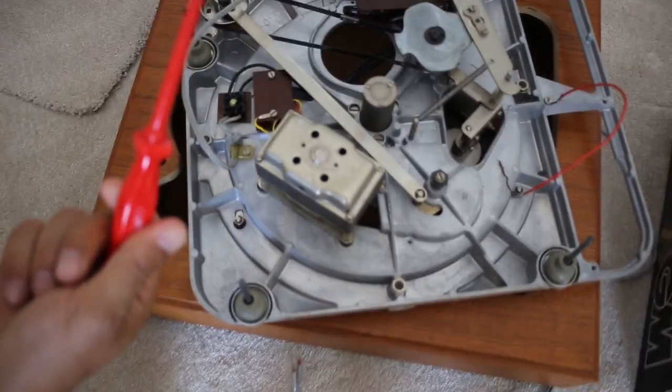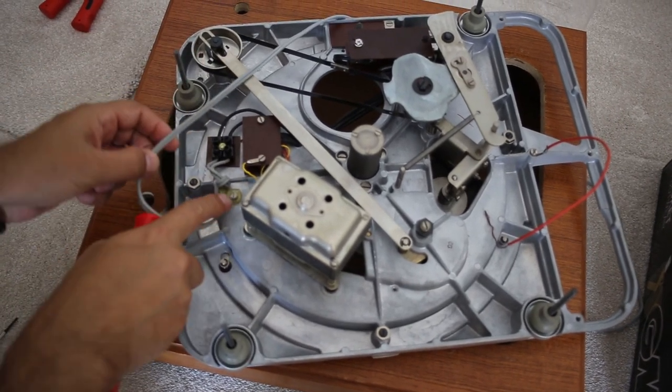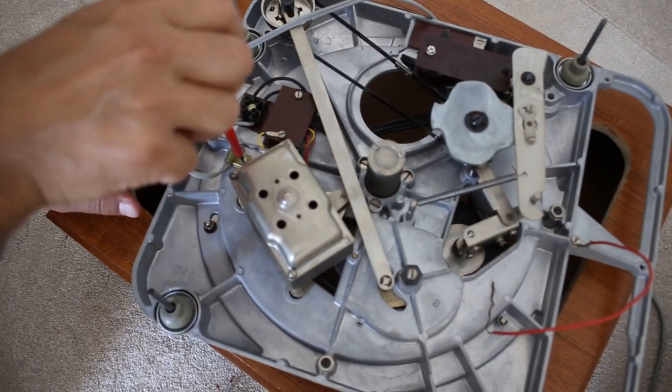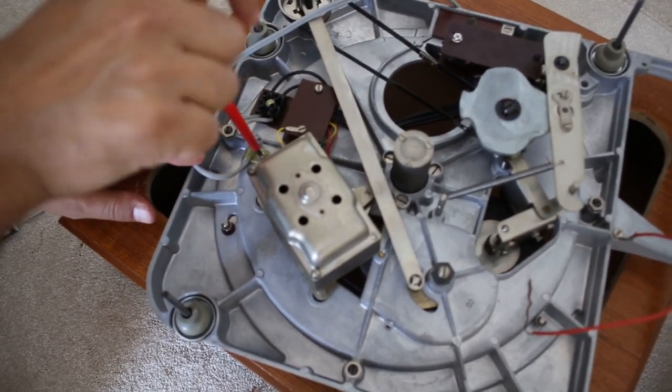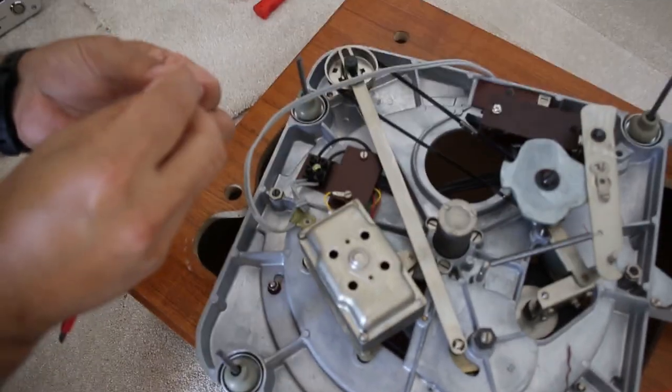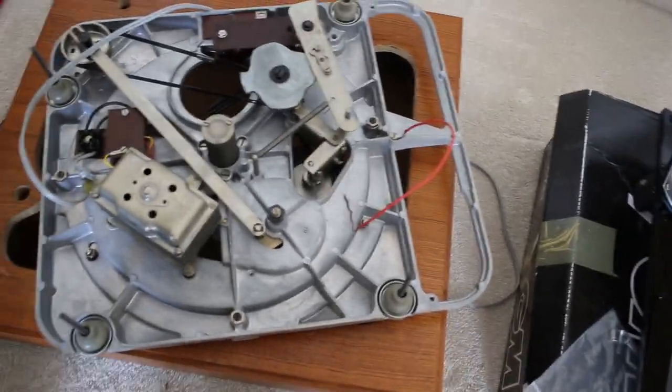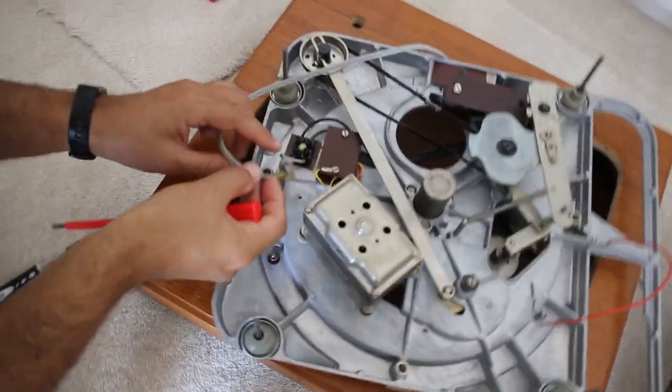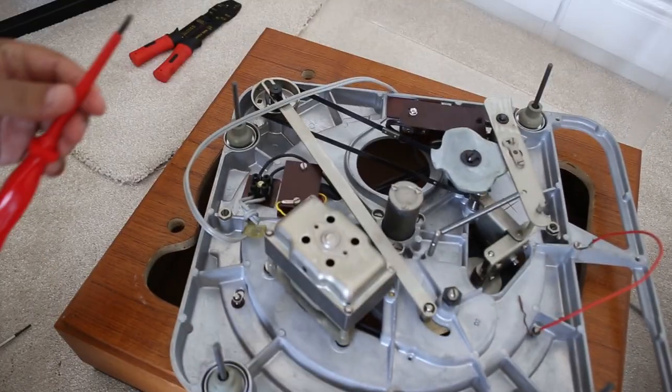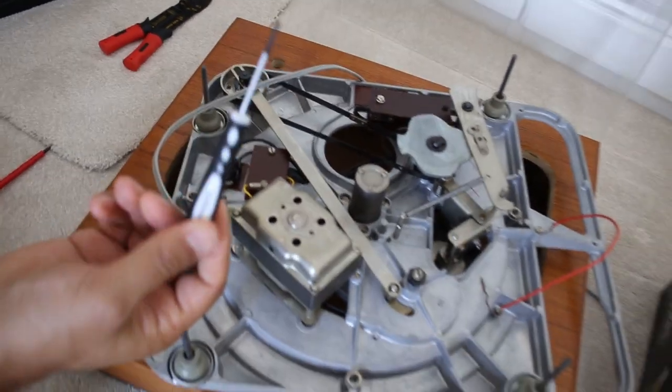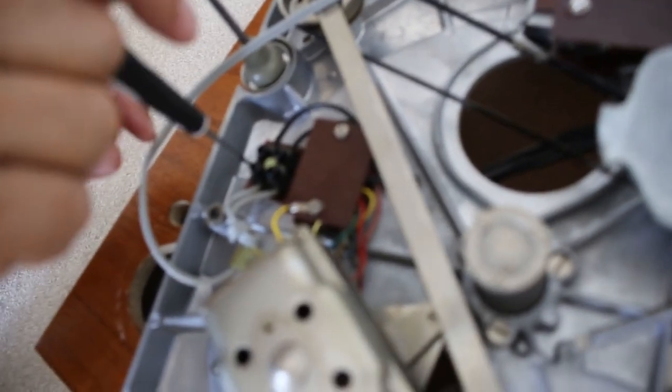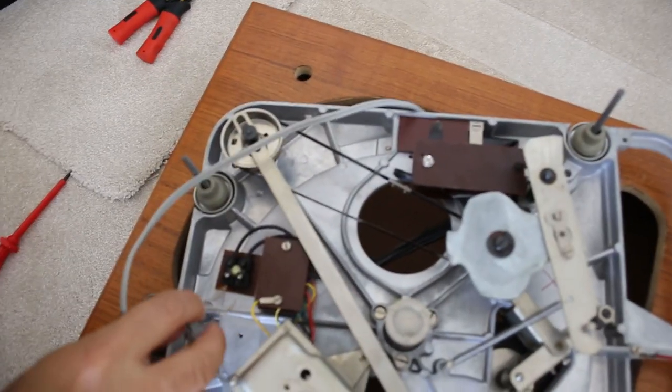So first thing is get your flathead screwdriver. And you remember this fastener here, before you get to the terminal block? So I'm going to loosen the fastener. It comes out pretty easily. Now keep that in a safe place because you're going to need it again. Right, now you get to the terminal block and instead of this big flathead screwdriver, you're going to need a smaller precision screwdriver, again with flathead. The terminal blocks, you're going to have to access from the top, and then what you're going to need to do is loosen them from the top like so. Don't take them all the way out, just enough so that you can dislodge the wires.